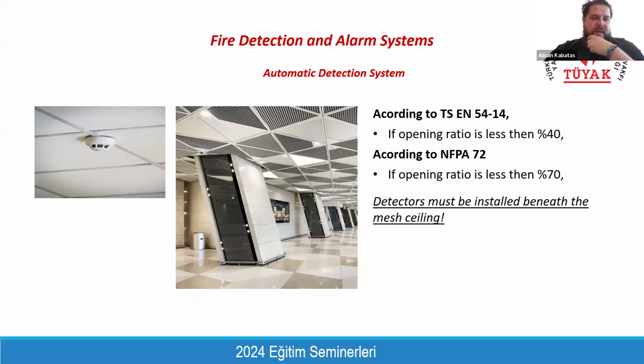And also, if you have this kind of grated ceiling, as we talked for the sprinkler system, if you would like to locate your fire detectors within the ceiling void and you don't want to locate them beneath the ceiling, then the ceiling opening ratio should be not less than 70% as per NFPA, but it is 40% as per European norm. If you'd like to omit fire detectors below ceilings, you need to take these opening ratios into account.